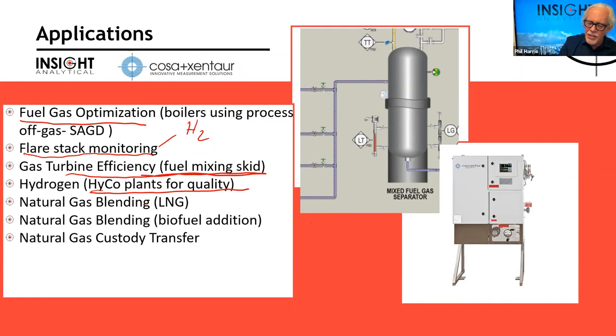Gas turbines is another one, especially when we're mixing in different fuels. If we have two different fuels we're going to mix together and then put them in the turbine, the mixing ratio is going to change the composition of the fuel and it's going to change the combustion air requirement. So whenever we're blending gases and we want to figure out how much air I now need to burn this, this is where a Wobbe Index analyzer comes into play. It allows you to stay at that optimum burn point.